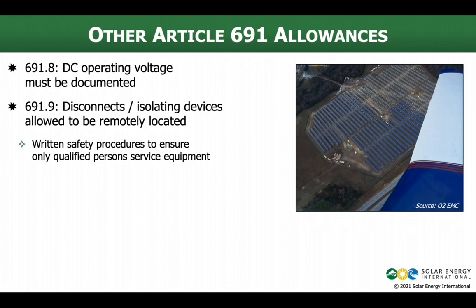Disconnects and isolating devices are allowed to be remotely located. Distance requirements in Article 690 don't apply as long as there's written safety procedures to ensure that only qualified persons service the equipment. We already said that fundamental to the definition of large-scale PV is it's only accessed by qualified persons, and we're going to have a written plan, the O&M plan, standard operating procedures for preventative maintenance, how we react for reactive maintenance. That is all going to be detailed and documented as part of the system O&M package.